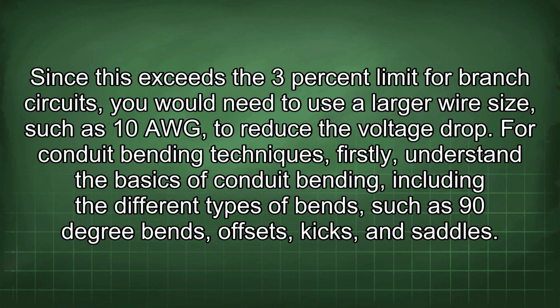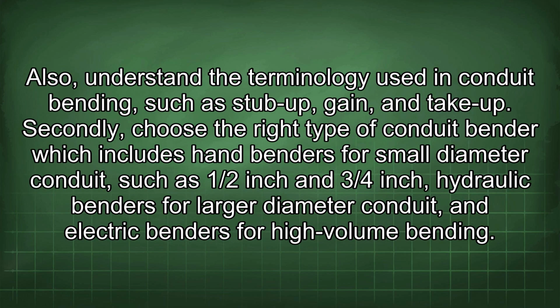For conduit bending techniques, firstly, understand the basics of conduit bending, including the different types of bends, such as 90-degree bends, offsets, kicks, and saddles. Also, understand the terminology used in conduit bending, such as stub-up, gain, and take-up. Secondly, choose the right type of conduit bender, which includes hand benders for small diameter conduit, such as 1/2 inch and 3/4 inch, hydraulic benders for larger diameter conduit, and electric benders for high volume bending.